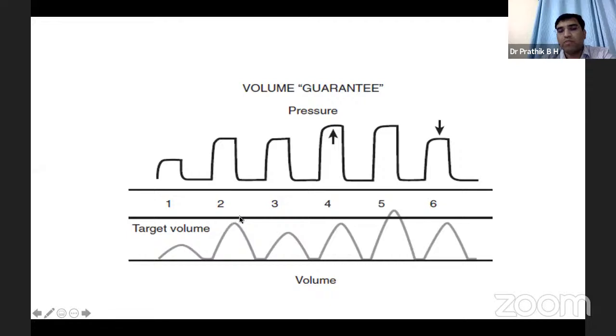Here the targeted tidal volume is almost achieved. But in breath number 3, again you can see that because of decreased patient compliance, the tidal volume target is not reached. Again, what the ventilator does is increase the peak inspiratory pressure so as to deliver the target tidal volume. And again, in the 5th breath, the same amount of pressure is delivered as in breath number 4.